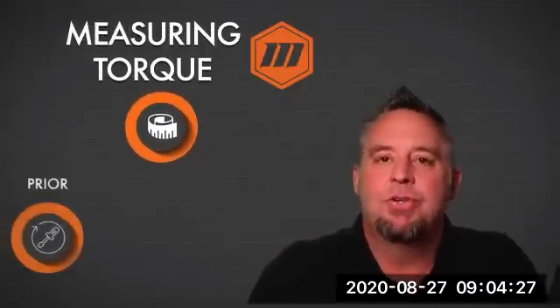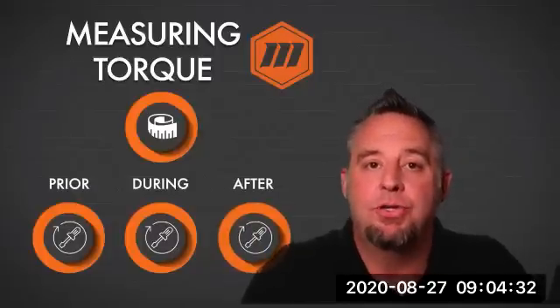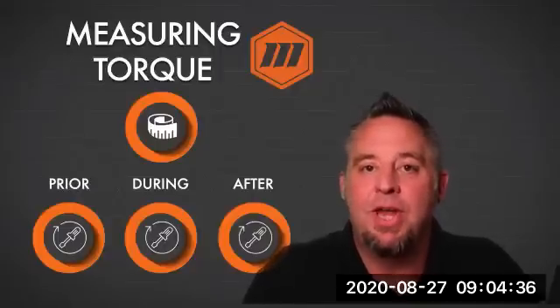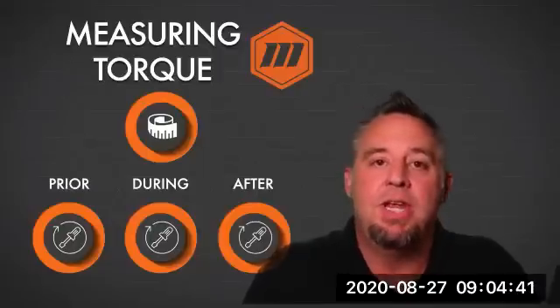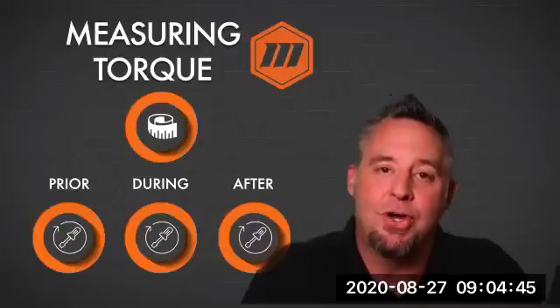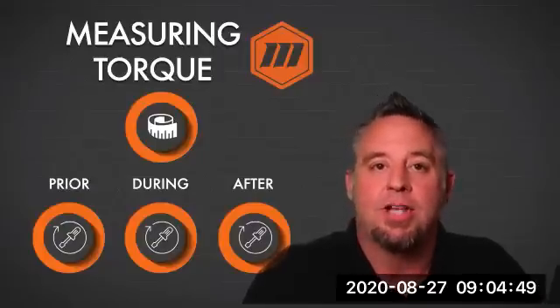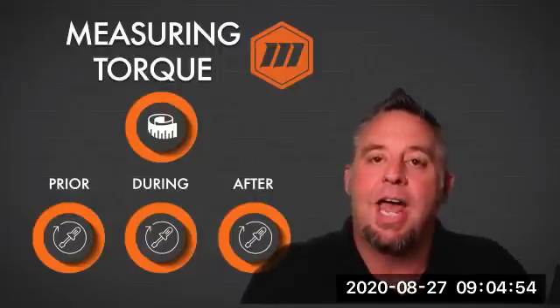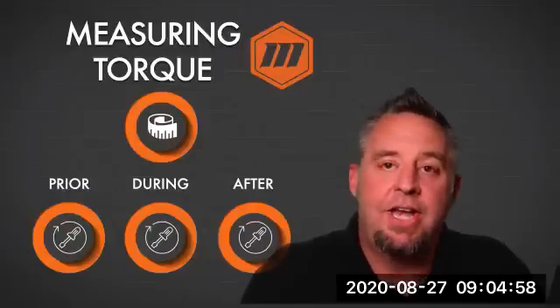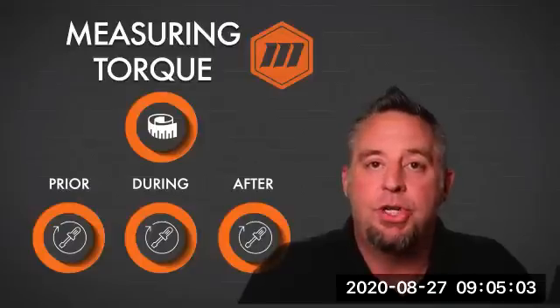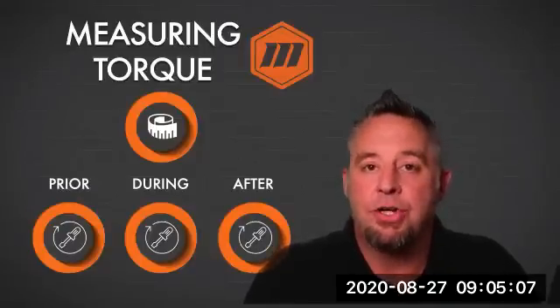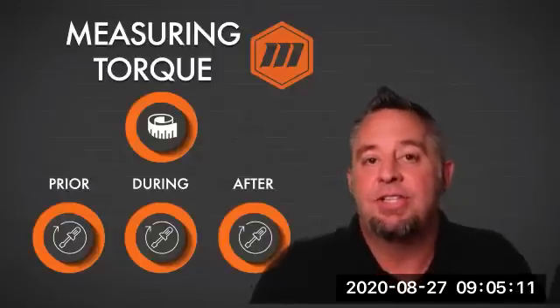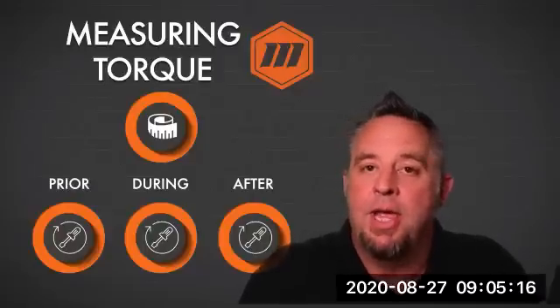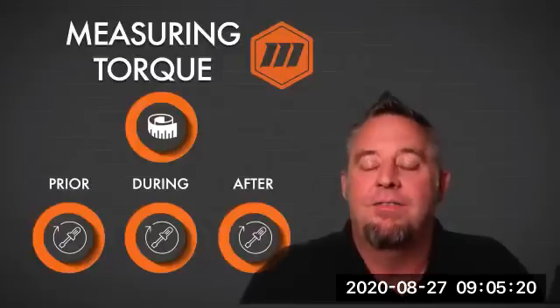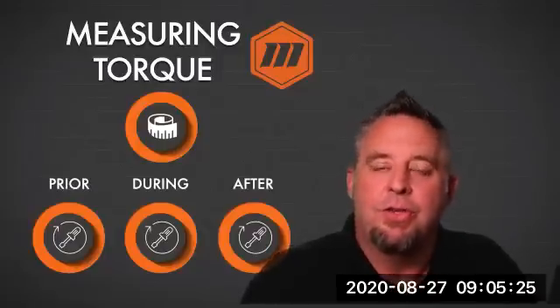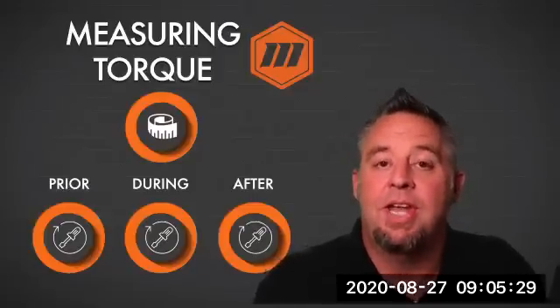So when we look at measuring torque, the question often is, when do I measure my torque? There are basically 3 different times that we can measure torque. The first would be prior to assembly, the second would be during the assembly process, and the third, after the assembly process. Prior to assembly, we're using it to calibrate our tools. We're also validating to make sure that the tools are performing the way that they are supposed to. During the application, we have the ability to monitor how the tools are performing using our measuring devices. And then after the fact, we can do auditing and use sensors to audit the assembly. So those are the different measuring times that we can use the certain devices.